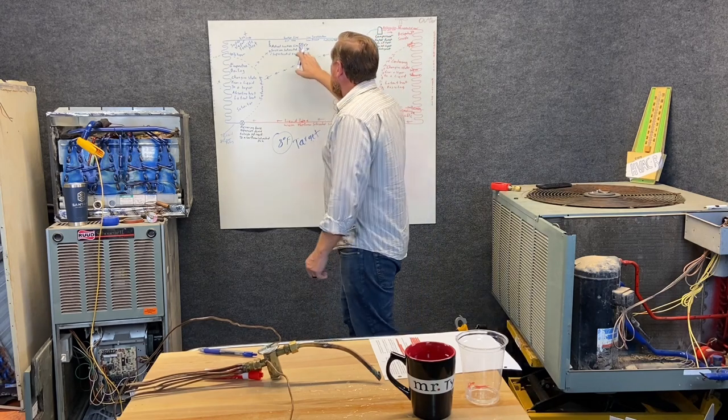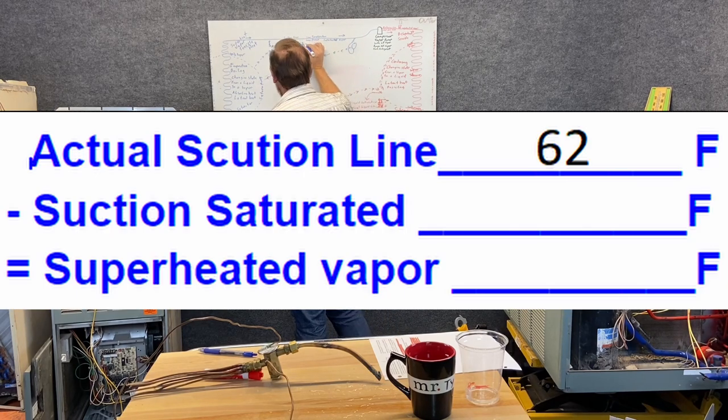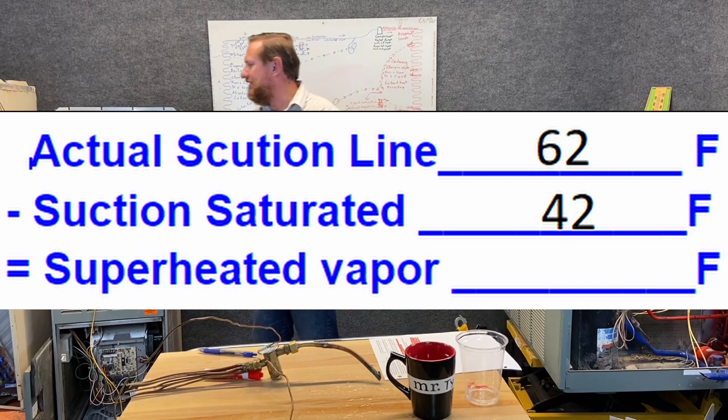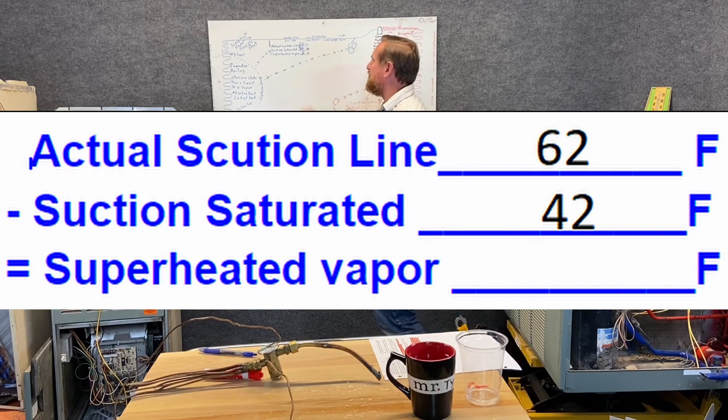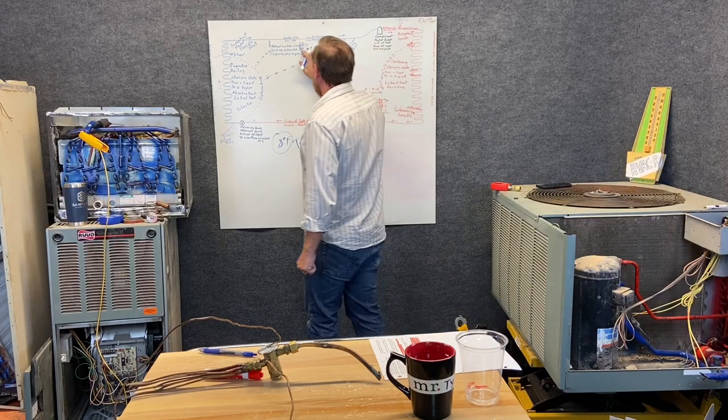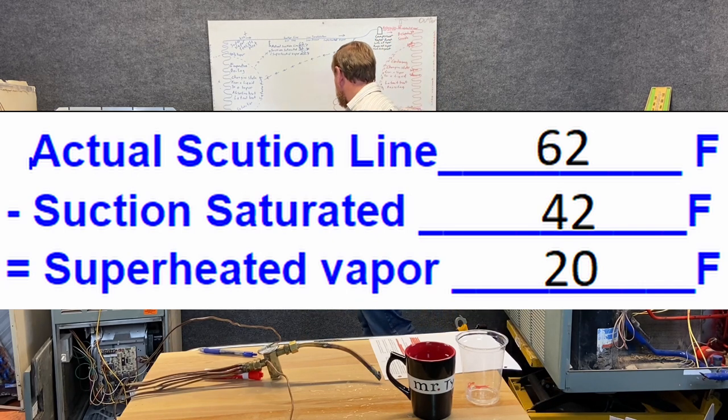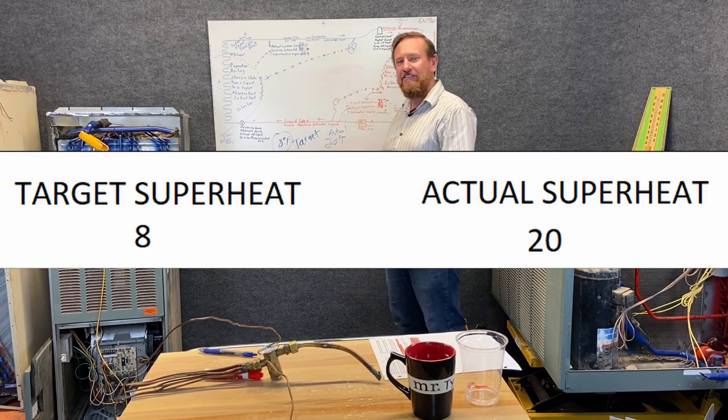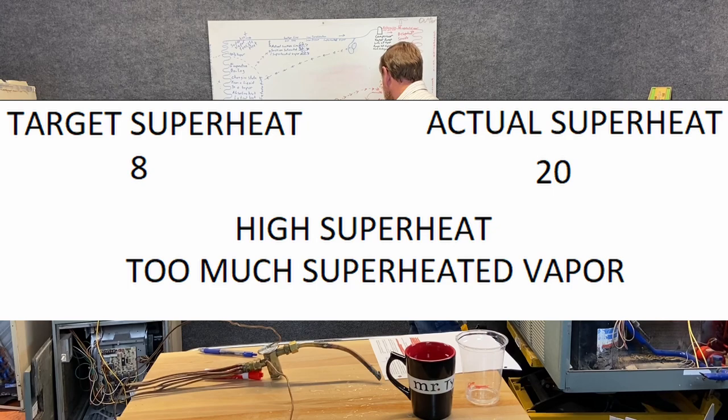Let's say that our suction line temperature was a different number. Let's say our suction line temperature was 62 degrees Fahrenheit. So if we take our PSIG converted to temperature, it's still at 42. But if we take our actual suction line temperature, it rose to 62. Well, if we take actual suction line temperature, 62, minus our suction saturated temperature of 42, we end up with a superheated vapor of 20 degrees Fahrenheit. That's outside of any of our range. So our superheat comes out to be 20 degrees Fahrenheit actual. That's much higher than our target of eight. This is called high superheat, high superheated vapor.